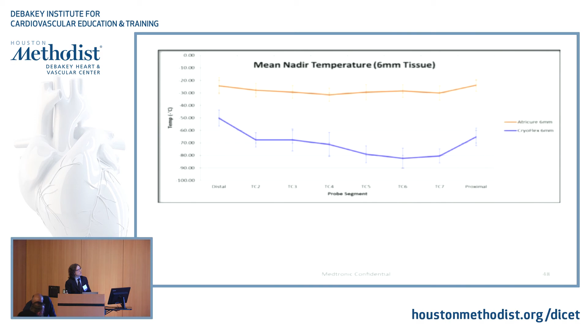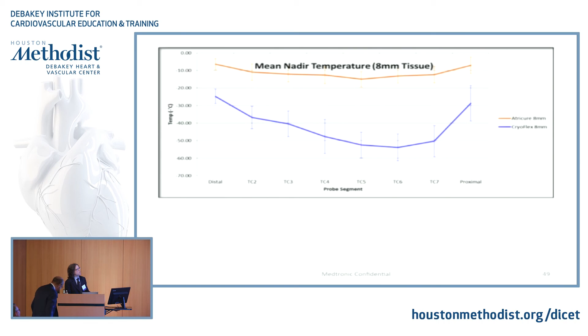And as a rule of thumb, I never freeze with a full 10 centimeters with a Cryo 2. I always freeze only 6, maybe 7 centimeters, because the proximal part, as you can see, can be much warmer. So the igloo effect is important, because if the tissue is not dry and you ablate fluid, blood, or whatever it is, you create an insulation. Basically, you are freezing something against the tissue, but it's not the probe against the tissue. The same applies when you freeze tissue, because then you have to push the ice ball forward, and the ice ball may isolate you if the tissue is too thick.